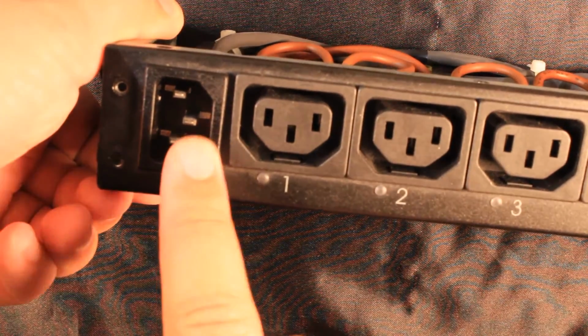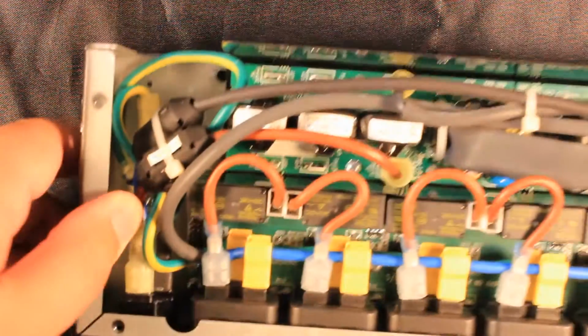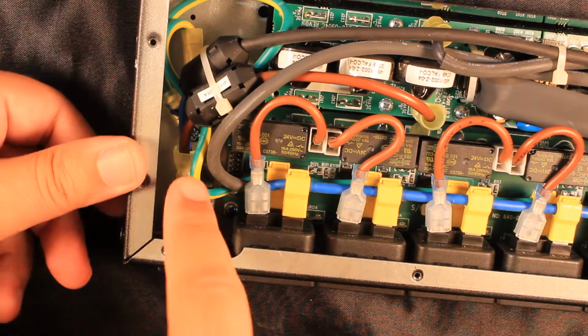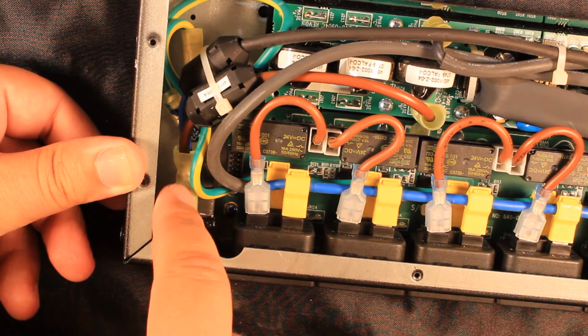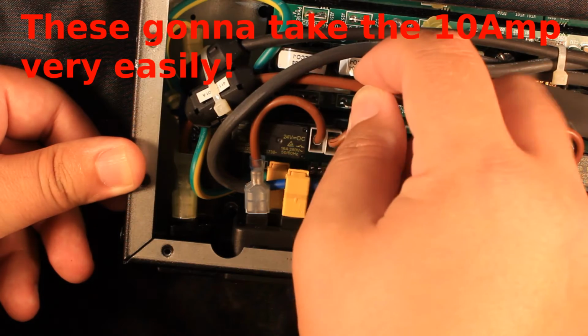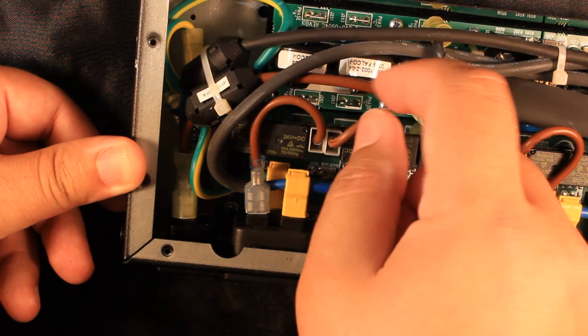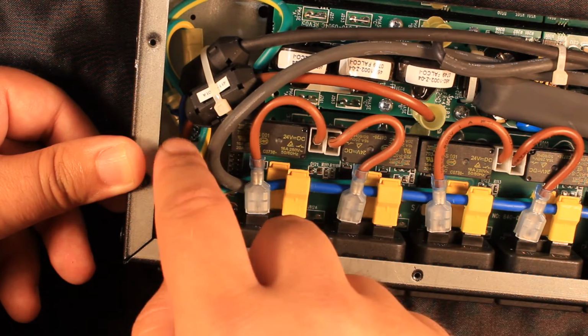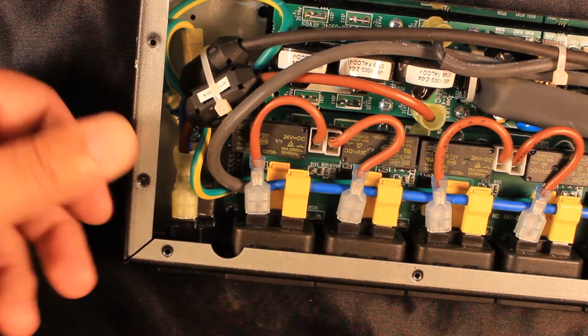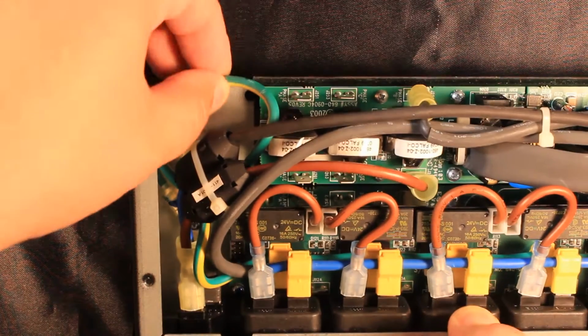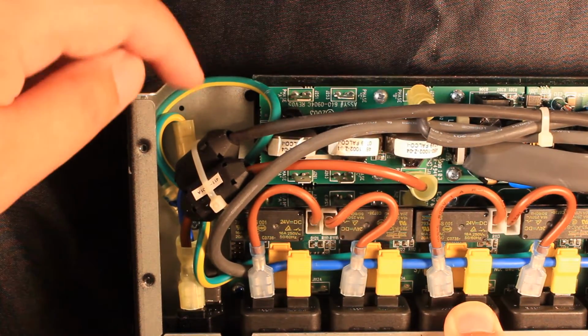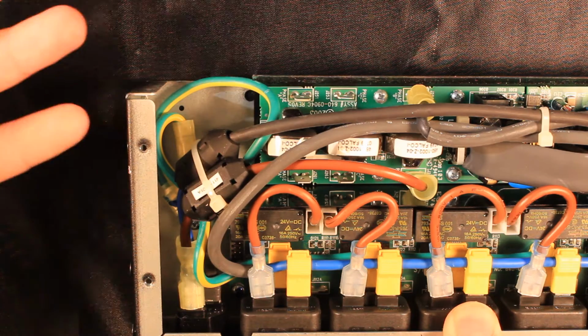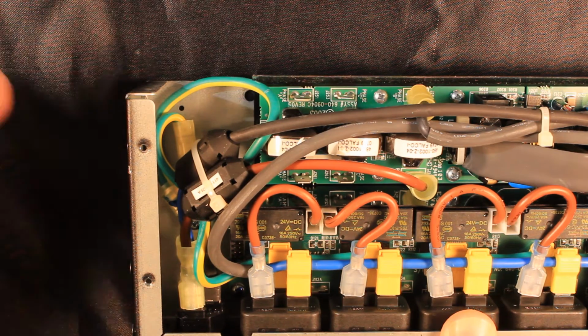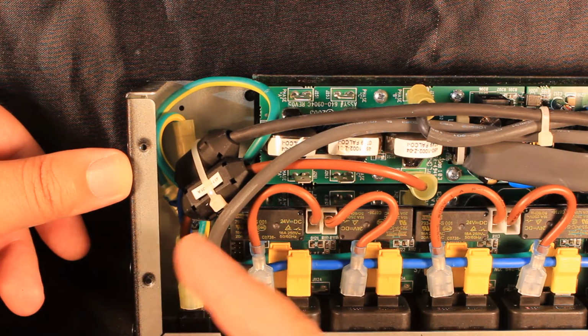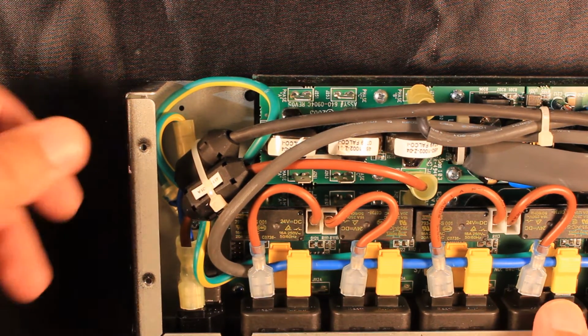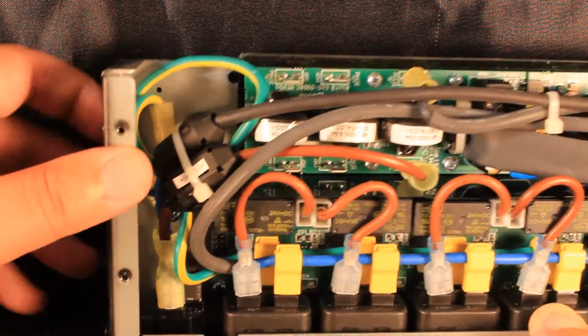Here is then the power input plug, and this power input plug is leading to two relatively thick power cables. So this would be the hot, and the blue one would be the neutral cable. Just look at this nice shake-proof washer thingy and the earthing. I mean, this is a proper job. This is what I would expect from a really well-established manufacturer like APC. So yeah, I'm loving the power input.